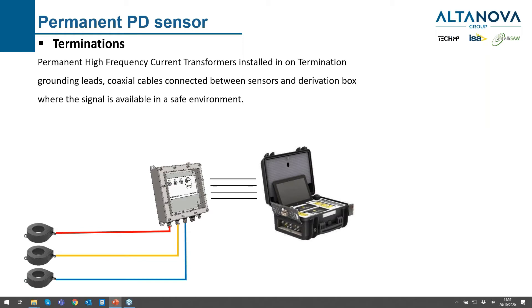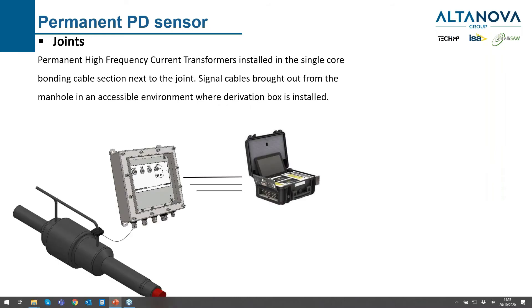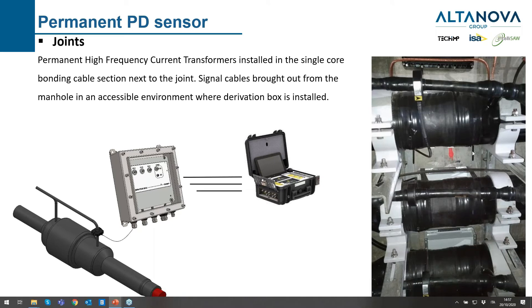On terminations, we can place high frequency current transformers (HFCTs). We have a schematic drawing on the left and a related picture on the right, where you can see the HFCT placed in the link box of a single cable termination. In the joints, HFCTs can also be installed — they should be placed on the single-core side of the bonding cable next to the joint, and the signal can be routed outside with a dedicated box.